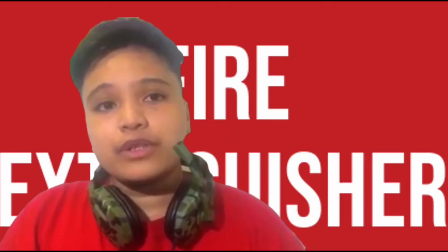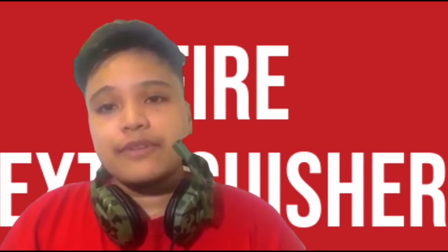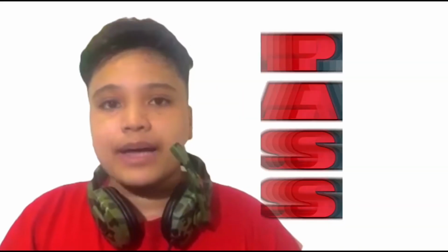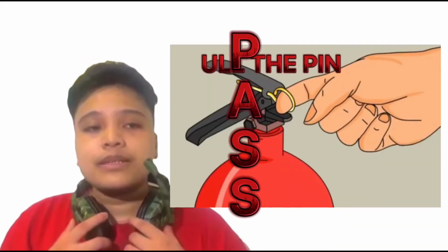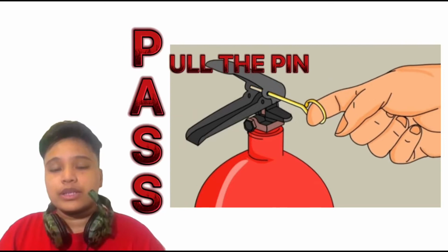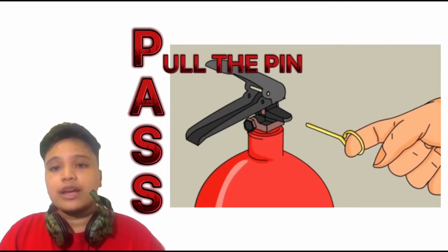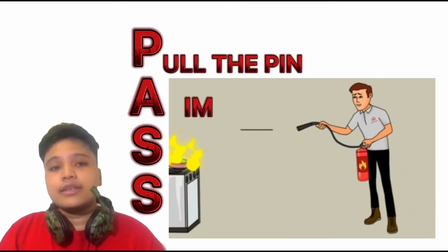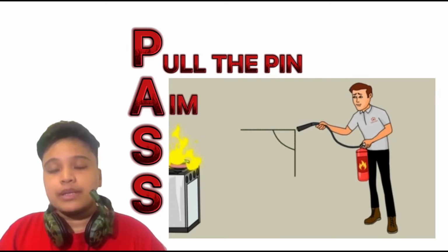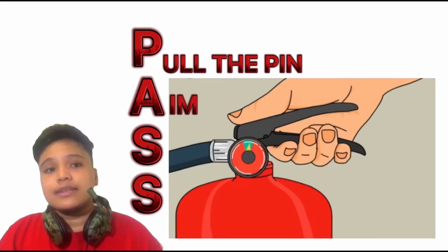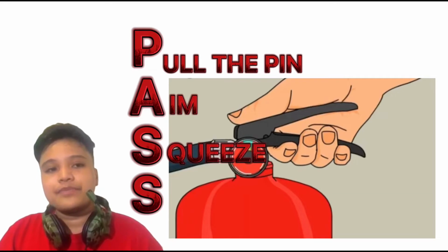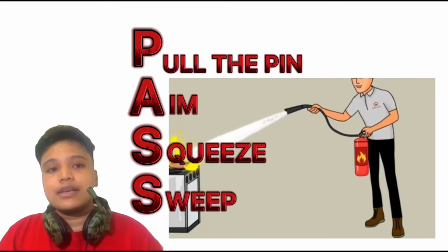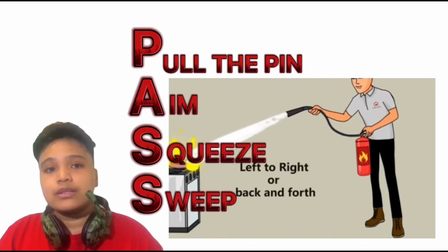So, let's proceed on how to use the fire extinguisher. For an easy-to-remember 4-step process to operating a fire extinguisher, learn the PASS system. P is to pull the pin while holding the extinguisher away from you to unlock the mechanism. A is to aim low toward the base of the fire. S is to squeeze the lever slowly. S, sweep the nozzle from side to side at the base of the fire.